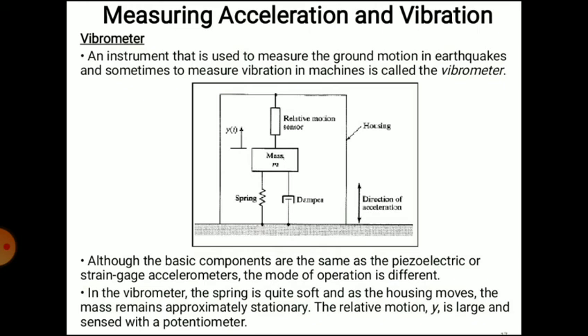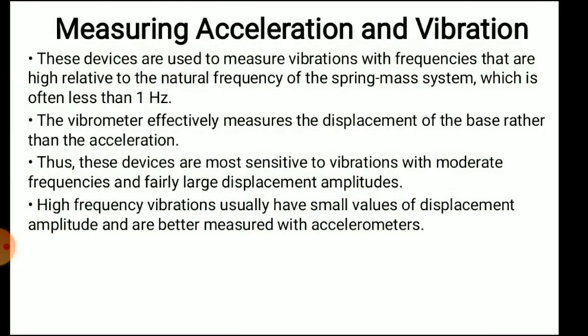Although the basic components are the same as the piezoelectric or strain gauge accelerometers, the mode of operation is different. In the vibrometer, the spring is quite soft, and as the housing moves, the mass remains approximately stationary. The relative motion y is large and sensed with the potentiometer.